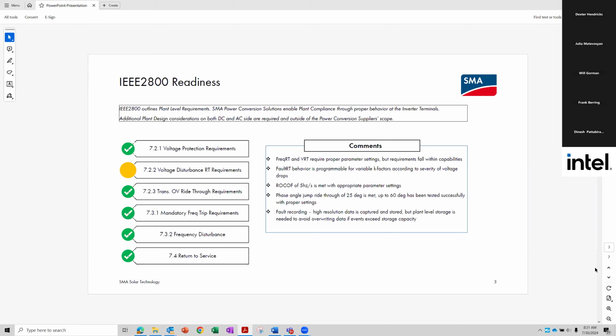The augmentation in IEEE 2800 is that there is now a further definition of exactly what the inverter behavior should be during a fault ride-through event. Looking at the major subsections under section 7, you have the voltage ride-through and protection requirements. Those are met by SMA equipment now, so no enhancements are needed in the equipment.